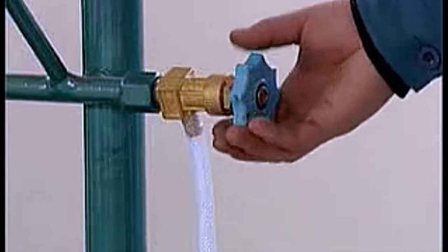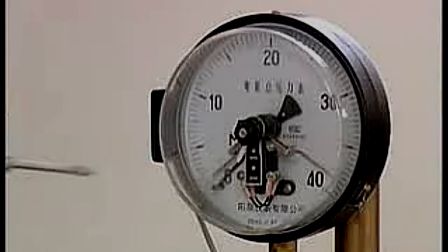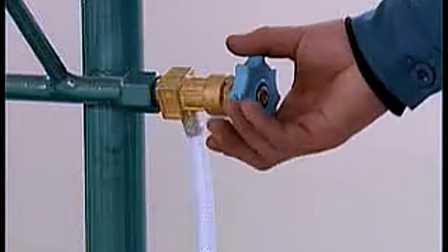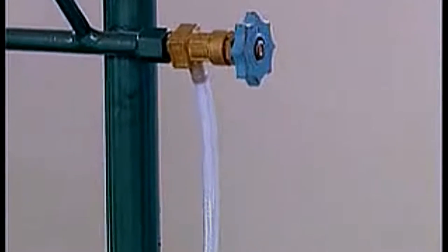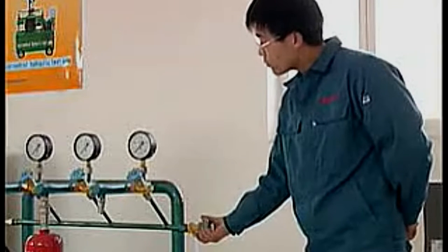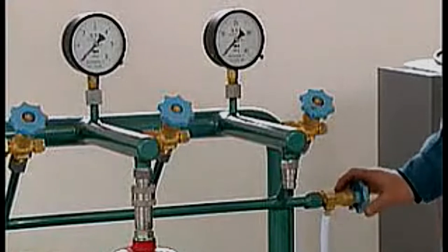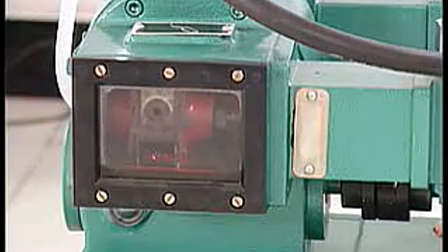Turn on electric hydraulic test pump. Open relief valve. Set test pressure in accordance with the hydraulic test pressure of the fire extinguisher. Close relief valve. Open drain tap of test stand to exhaust. Close relief valve when vent water is seen. Repeat thrice of exhaust press.